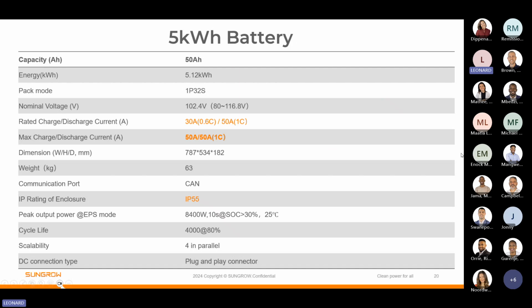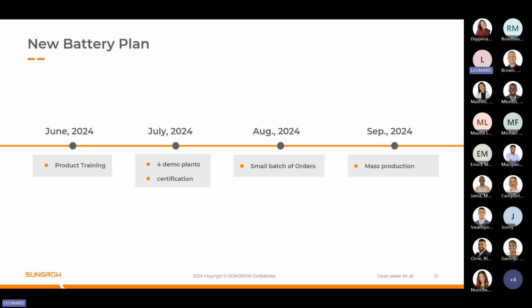Then just in terms of the technical data, this will be a 5.1 kWh solution. It will also be a 50 amp charge and discharge with a 1C application. It will be IP55, and the cycle life would be 4,000 cycles at 80% depth of discharge, since it's a 1C application. So obviously you can't use the full capacity of the battery as with the SBH and SBR solutions.